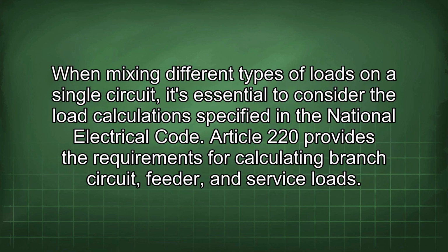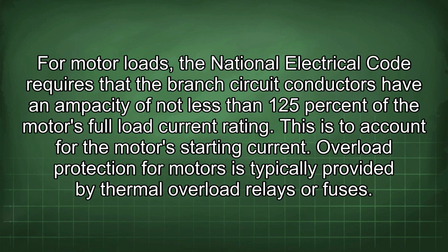When mixing different types of loads on a single circuit, it's essential to consider the load calculations specified in the National Electrical Code. Article 220 provides the requirements for calculating branch circuit, feeder, and service loads. For motor loads, the National Electrical Code requires that the branch circuit conductors have an ampacity of not less than 125% of the motor's full load current rating. This is to account for the motor's starting current.